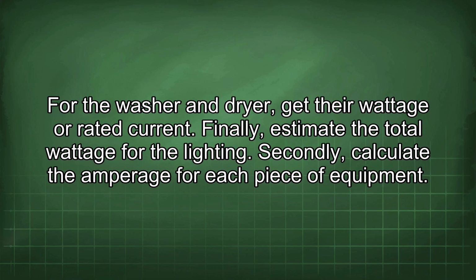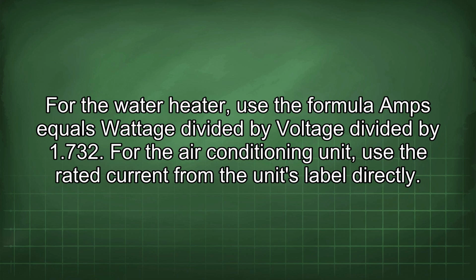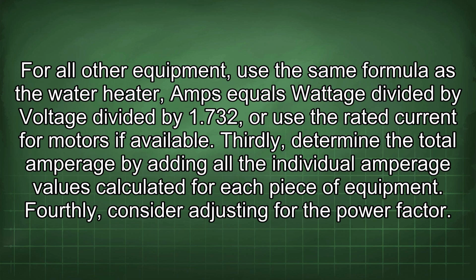Secondly, calculate the amperage for each piece of equipment. For the water heater, use the formula amps equals wattage divided by voltage divided by 1.732. For the air conditioning unit, use the rated current from the unit's label directly. For all other equipment, use the same formula as the water heater, amps equals wattage divided by voltage divided by 1.732, or use the rated current for motors if available.